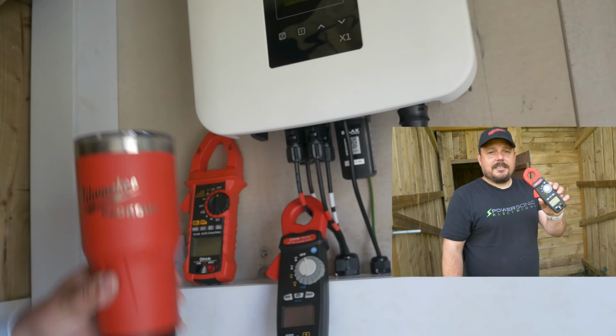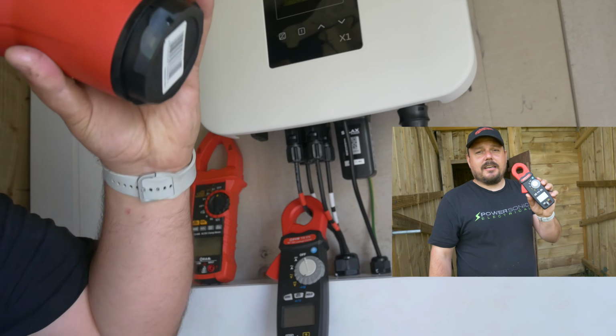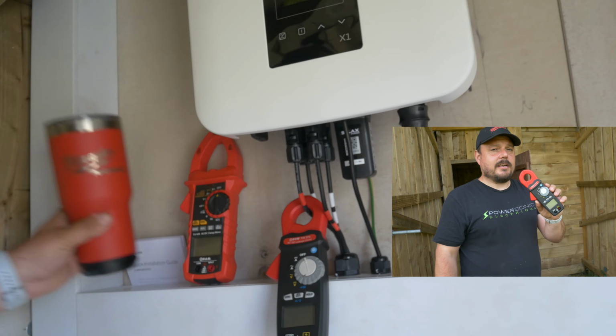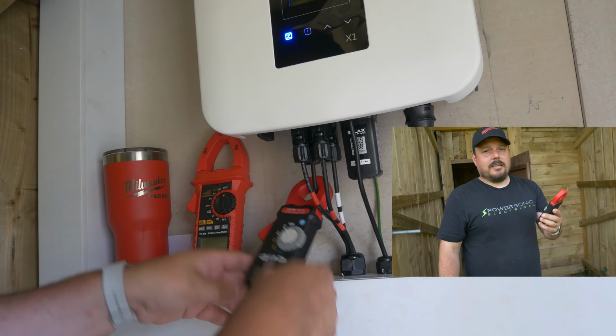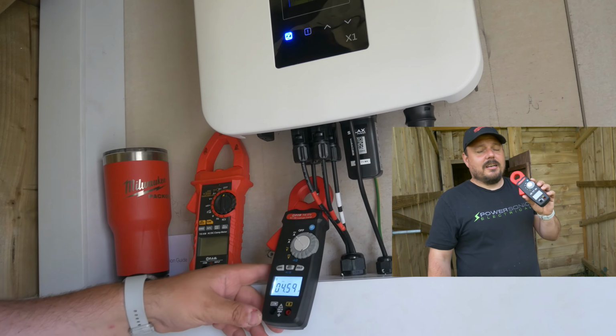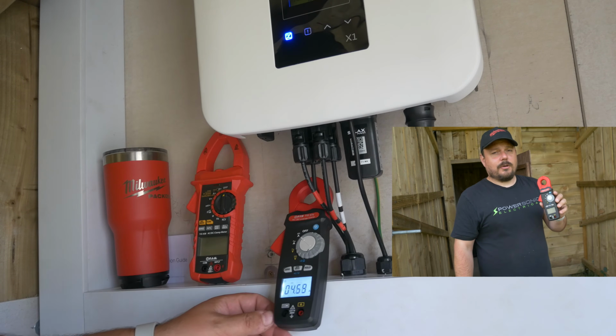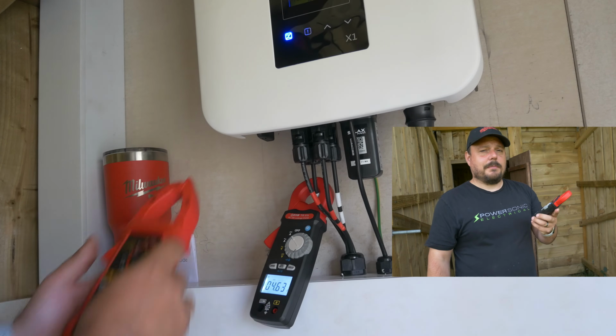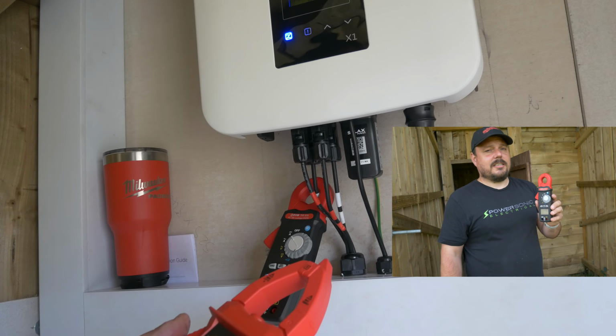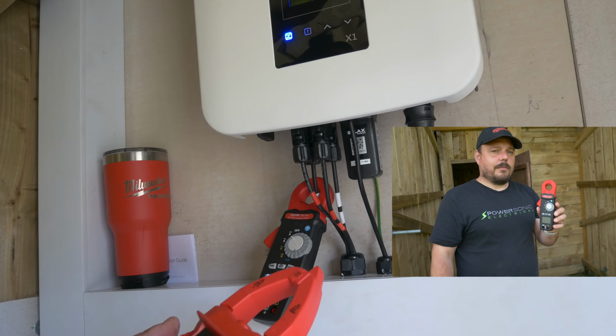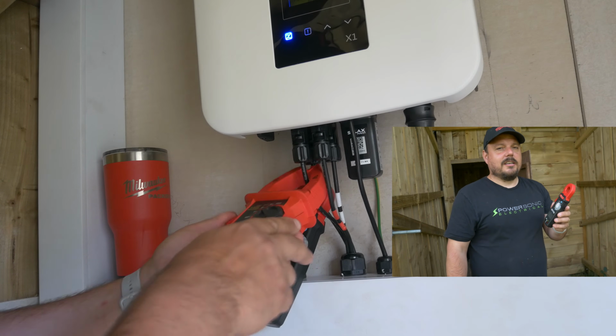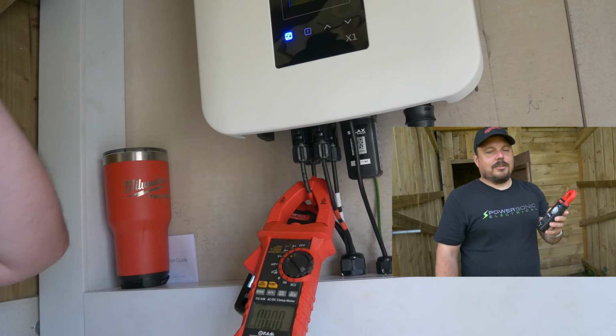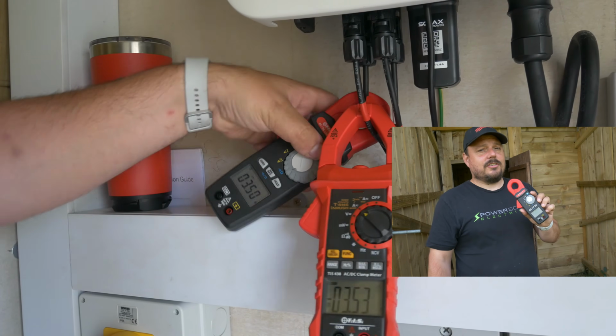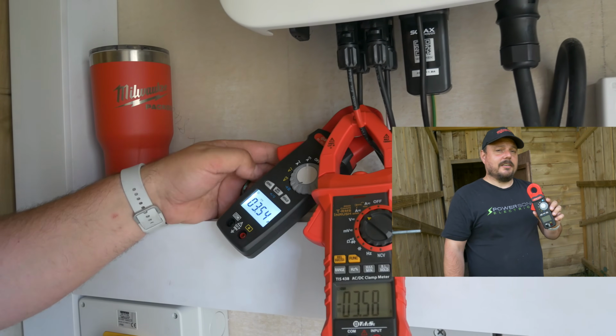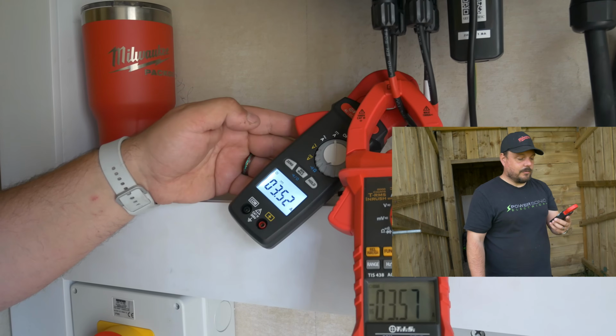Then we've got the clamp meters. This one is the TIS 570, and you'll have seen me using this a lot on the channel already in AC systems in domestic and commercial premises. These are really handy for seeing what current's flowing in an earthing conductor, for example, so you can see any DC or AC leakage to help identify a problem with maybe a blinded RCD, or excess leakage current upsetting RCDs, and just to see what current might be present in an earthing conductor before you go interfering with it.